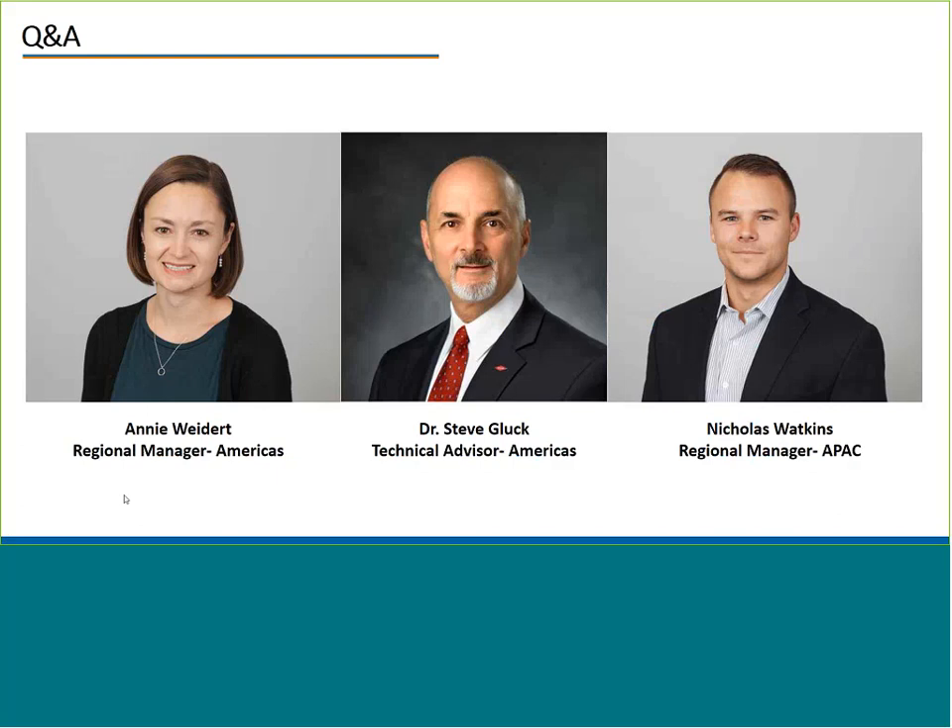Steve and Annie, I've got a list here — I'm just going to read out a couple as they come through. Steve, I might throw the first one to you. There's a question asking how often the units need to be cleaned and what's involved. Well, that depends on the loading and the type of pretreatment, but in general our operators find that once a month is sufficient. What's involved is lifting the lid, doing an inspection, and spraying off accumulated solids at the top and between the gills with a garden hose. Those solids drop into the recirculation tank and a valve at the bottom is opened to discharge them so they don't recycle back into the unit.